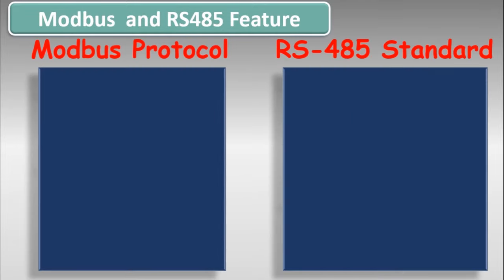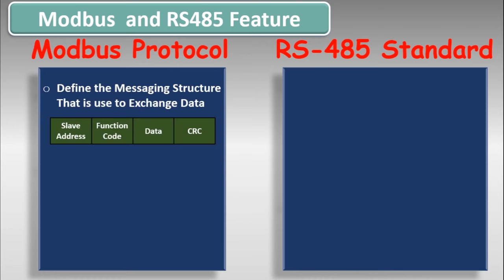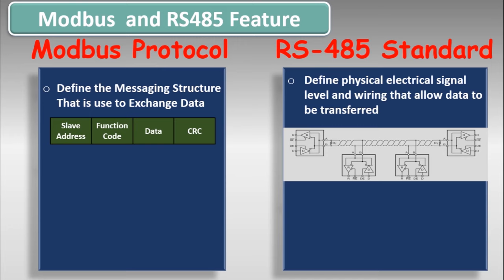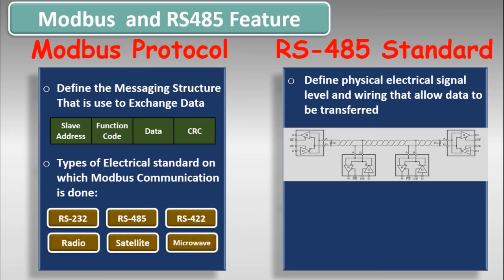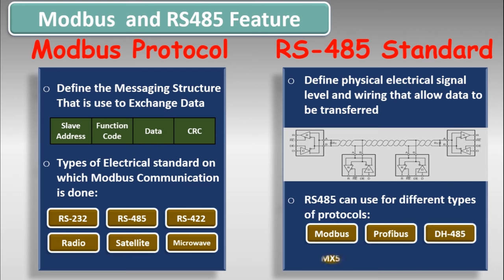Before going to the communication parameters, let me summarize the discussion on Modbus protocol and RS485. Modbus protocol is a messaging structure used to exchange data between two devices. RS485 defines the physical electrical characteristics of the driver and receiver, including wiring, that allow data to be transferred. Modbus protocol is not only tied to RS485 — it can run on RS232, RS422, radio, satellite, microwave, TCP/IP, and others. Similarly, RS485 can be used with other protocols such as Profibus, DS485, Optomux, DMX512, DCC, etc.